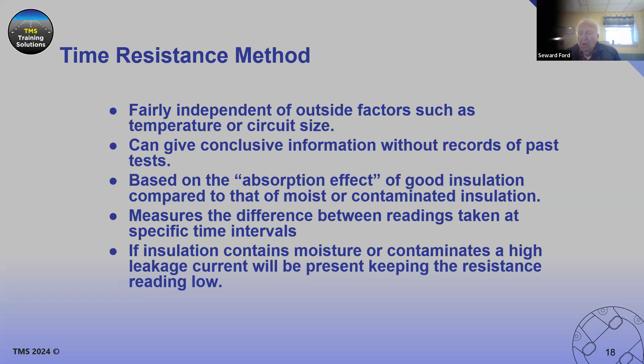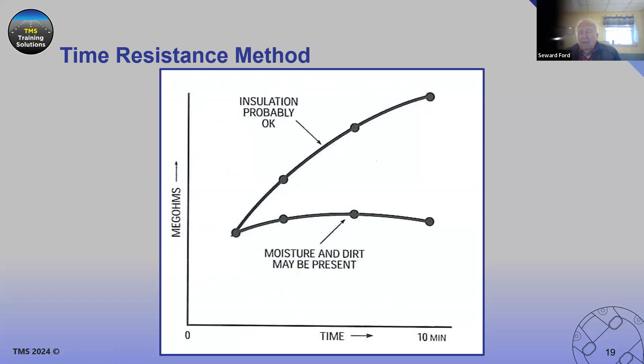Now, if we look to the next slide, we'll see there's a graph that was made up on a particular circuit, taking readings at particular points at different times. And you notice the insulation probably okay line there is that the Megger reading is continuing up during this 10-minute period on this test. But notice the other one is starting to trend down. That indicates that we've got some weak points in our insulation, and it may be moisture and dirt in there that is helping to make a path for that current to break through the insulation. And so that's another test you could do if you wanted to try that and see what difference the different readings were.